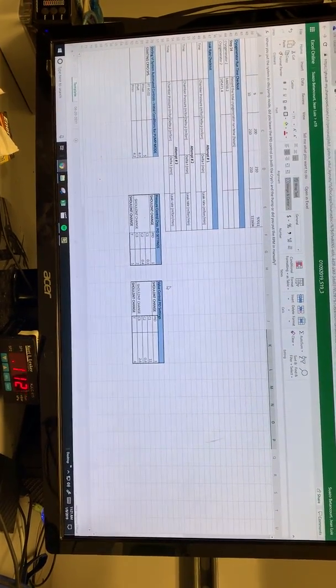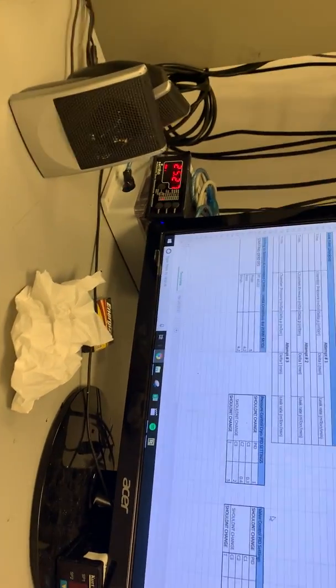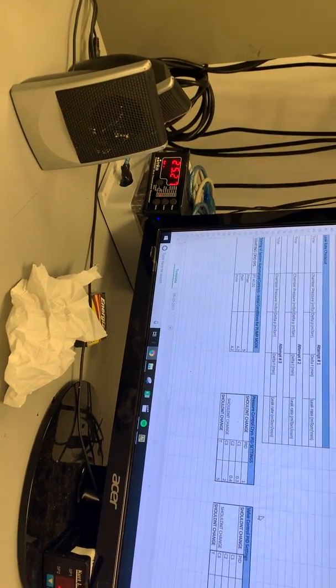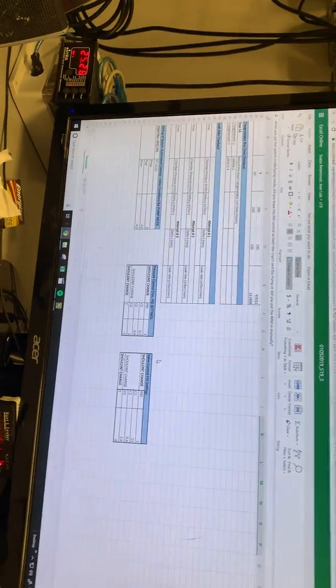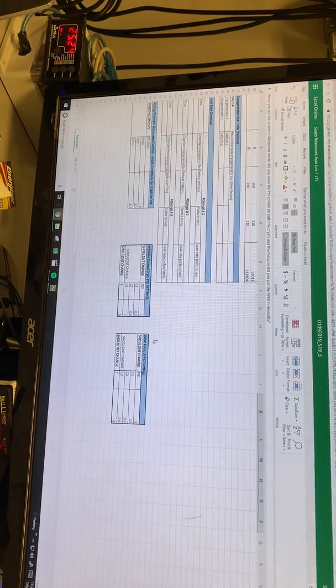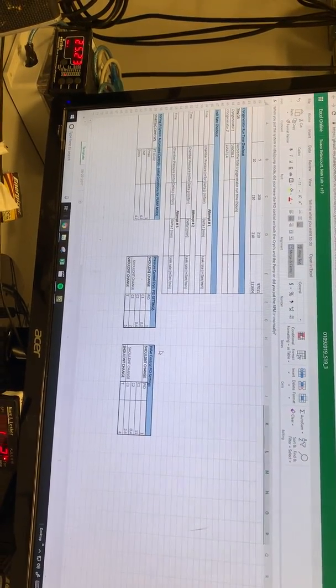All right, so now you've basically been roughing for a couple of hours here, and you want to look for something on the order of 20 to 25 millitorr before you try to start taking leak checks. Mind you, all this stuff should be plugged in, but I'm assuming that you're a grad student, so if something is unplugged, you'll be able to figure out how to plug it back in and connect it to the computer, etc.